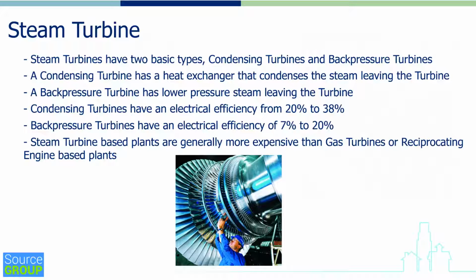Condensing turbines, as I stated earlier, have a higher electrical efficiency and can range anywhere from 20% for smaller turbines on up to 38% for very large, efficient turbines. Back pressure turbines, on the other hand, have a relatively low electrical efficiency and range somewhere between 7 to 20%. Steam turbine base plants are generally more expensive than gas turbine or reciprocating engine base plants.